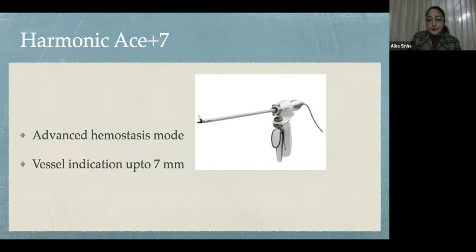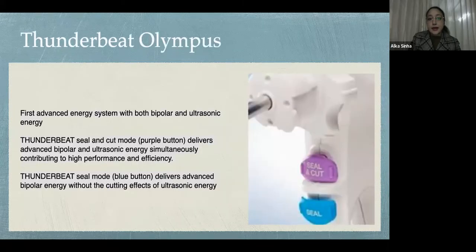Coming to some of the other devices, the Thunderbeat by Olympus was perhaps the first advanced energy system which delivered both bipolar and ultrasonic energy. The seal and cut mode, the purple button, delivers advanced bipolar and ultrasonic energy simultaneously, doing very efficient sealing and cutting. Whereas the blue button, the seal mode, delivered just advanced bipolar energy without the cutting effects of ultrasonic energy.